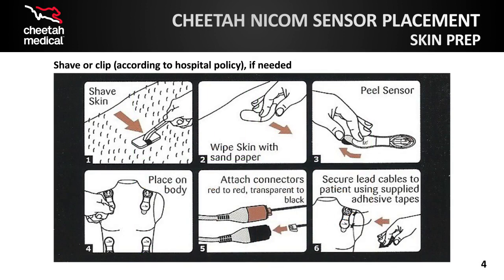Let's review the steps that are included with the instruction card for proper sensor application. 1. Shave or clip body hair if needed, according to hospital policy. 2. Wipe the skin with sandpaper for optimal adhesion. 3. Peel the sensor. 4. Place the sensor on the 4 quadrants of the body. 5. Apply connectors. 6. Secure the lead cables to the patient using supplied adhesive tape, Tegaderm, or other similar products which you have access to in your hospital.